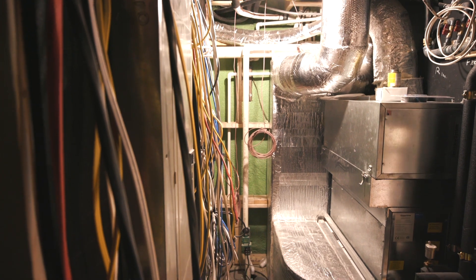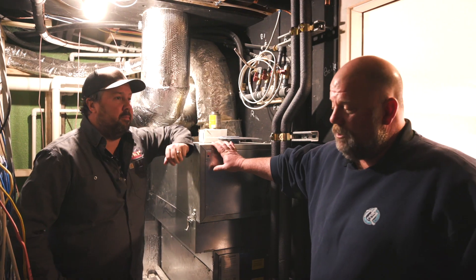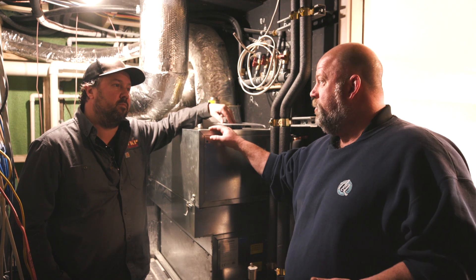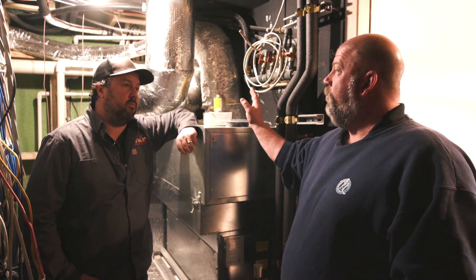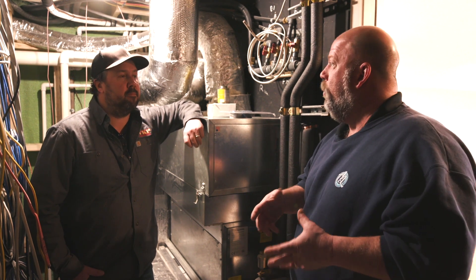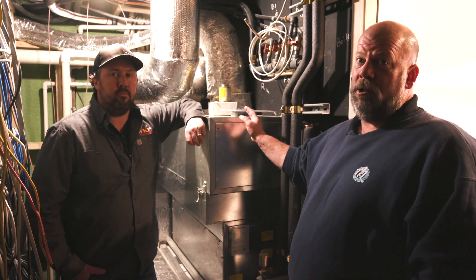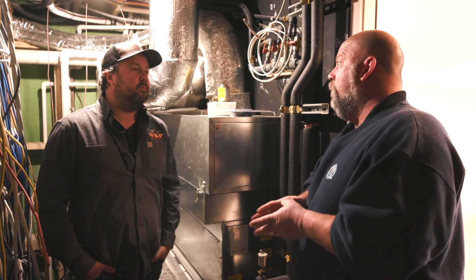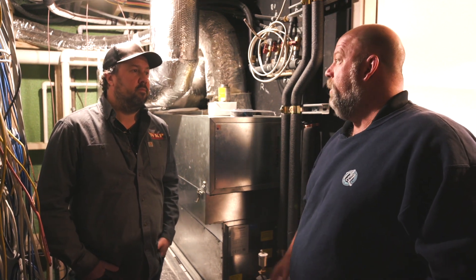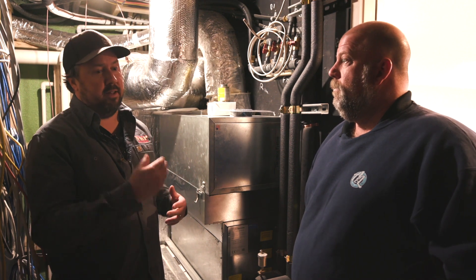What can people know who are hesitant about using a Unico system that could give them some peace of mind? Well, the Unico systems are high-velocity — the air moves a lot faster than in conventional systems. What Unico has done to help alleviate that is running a nine-inch main duct on the supply instead of the old six-inch duct. That gives a little more air surface and slows the air down. We also now recommend a minimum of seven outlets per ton on the Unico. With seven outlets, we do the full 12-foot sound attenuator on every run to reduce noise and slow the air down. That's been working exceptionally well, with no complaints from previous clients.